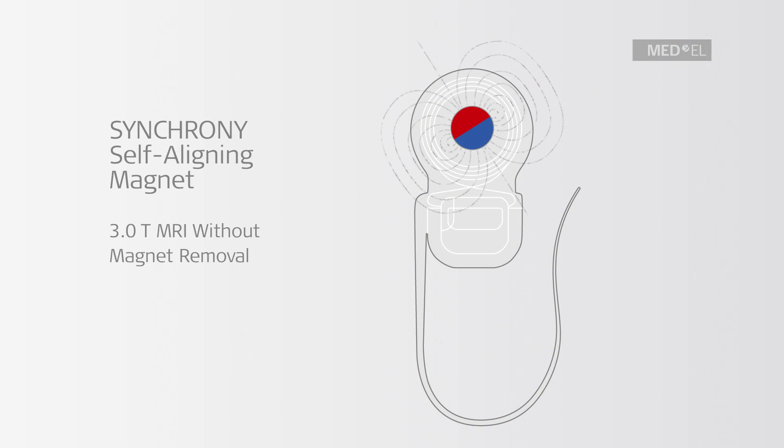Our synchrony cochlear implant has a unique self-aligning magnet that rotates and aligns with the magnetic fields in a scanner, so there is almost no magnetic torque, even at 3 Tesla.